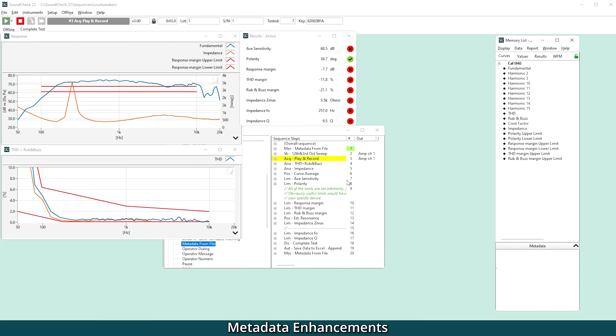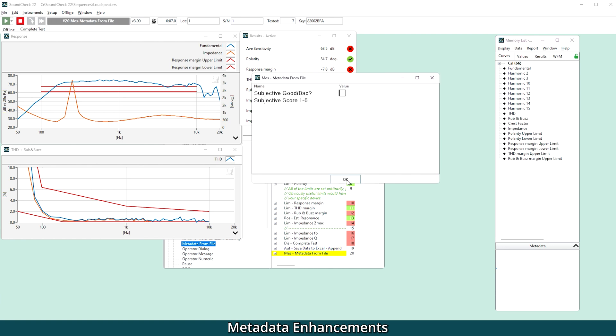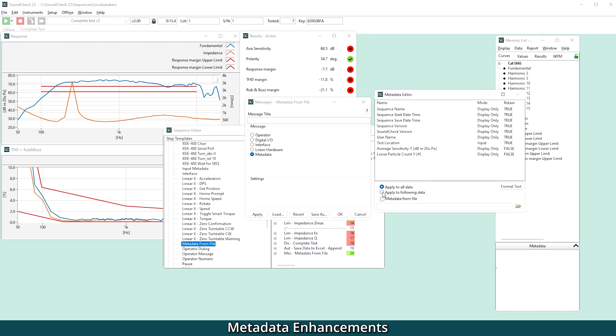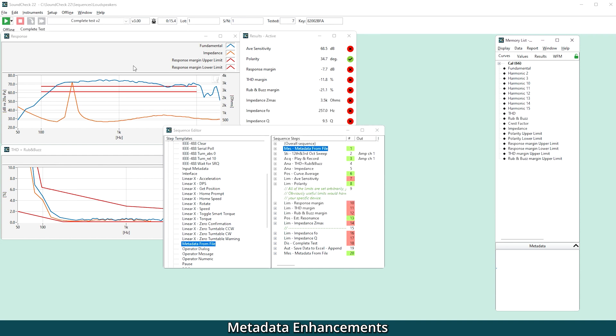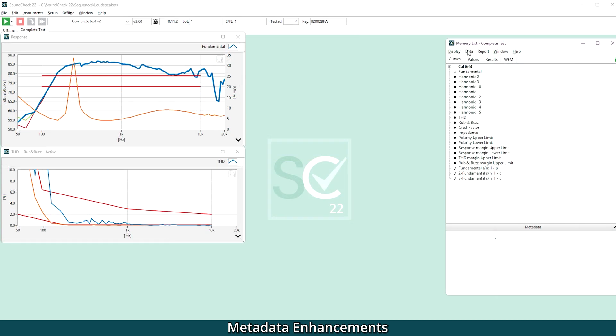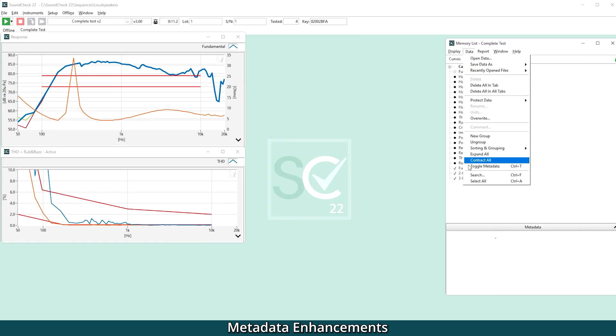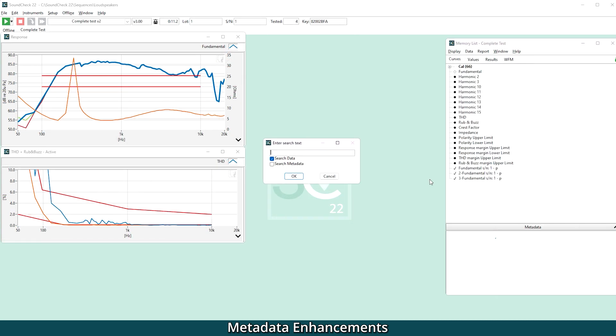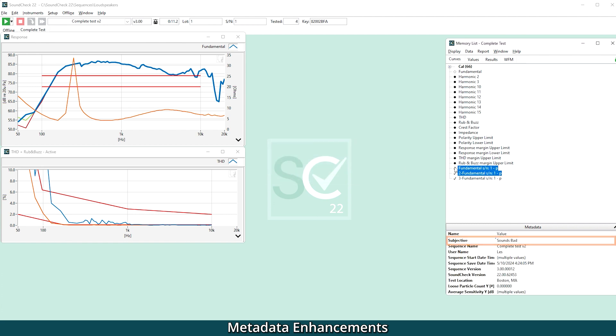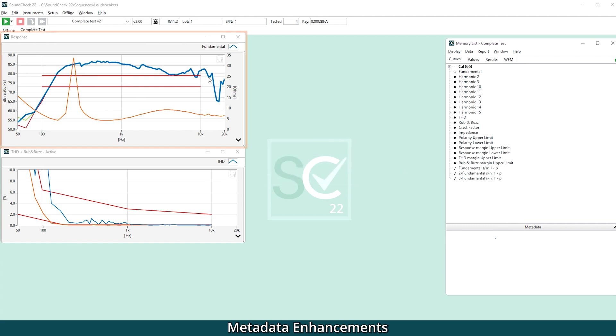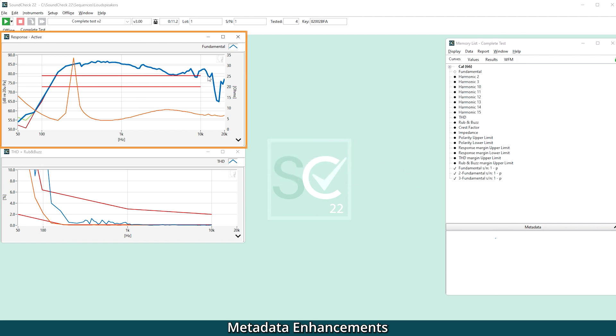This step can also be used at the end of a sequence after the measurement to allow the user to input information regarding the DUT. For example, a subjective opinion of the sound quality during the test sweep. Metadata can even be loaded from a file in the editor if there's a lot of information that needs to be entered. It's easy to identify results by metadata as we've now added the ability to search metadata in the memory list. You can even display the metadata of any selected curve simply by selecting it in the display window.